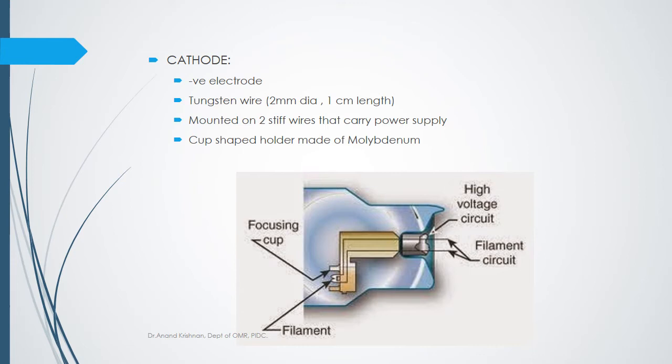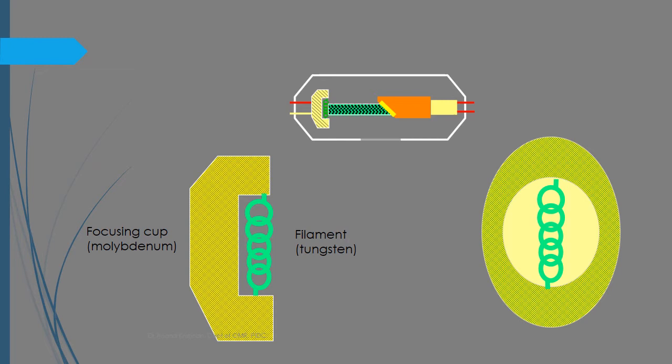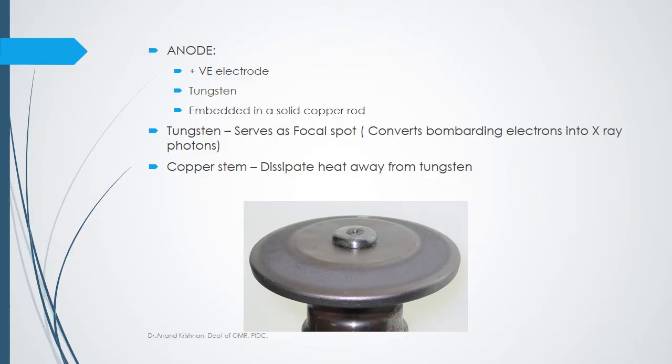The cathode is negatively charged and made of a tungsten wire approximately two millimeters in diameter and one centimeter in length, mounted on two stiff wires that carry the power supply. It is mounted in a cup-shaped holder made of molybdenum. A cross-sectional view shows how the cathode is positioned within the molybdenum cup.